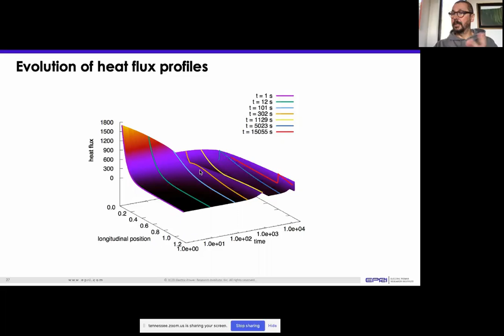And in fact, here you go - for about 3 hours you charge your system. So you have a 6 kilowatt thermal, remember we're competing with a 2 kilowatt electric, so that's about 6 kilowatt thermal. You're transferring heat at a constant rate until you run out of stuff to freeze, and then it drops off pretty quickly.